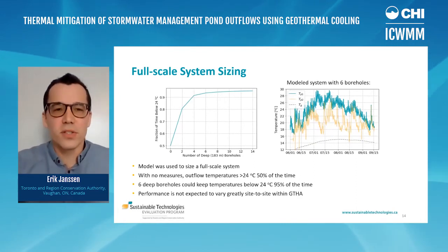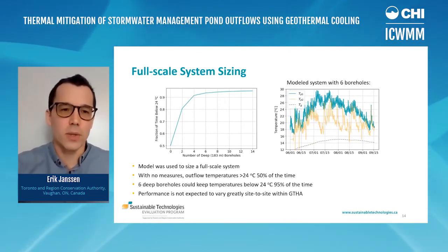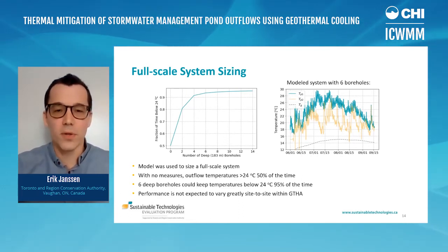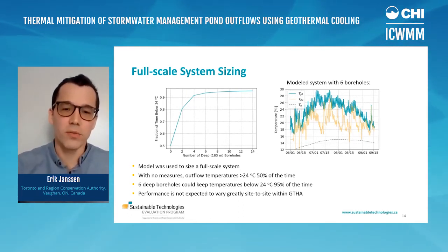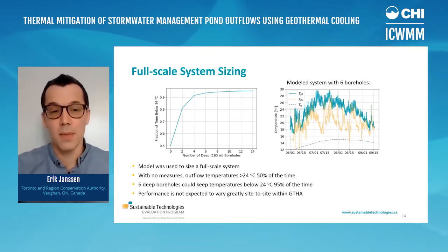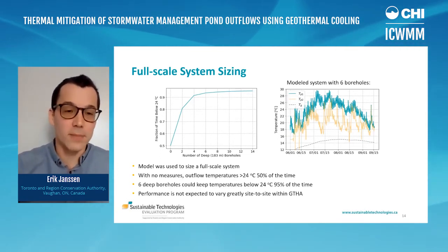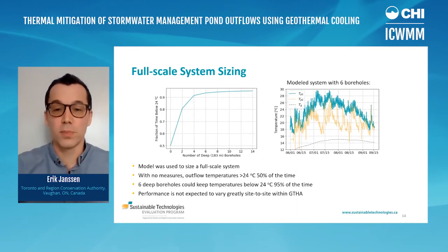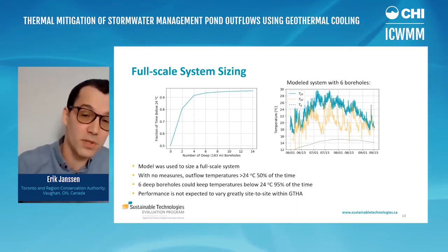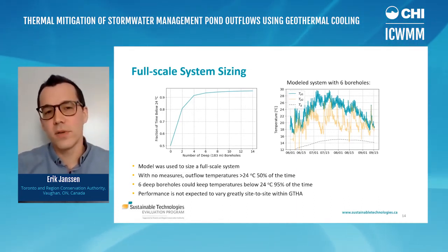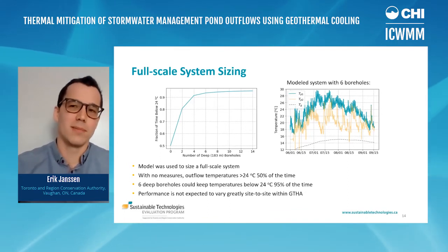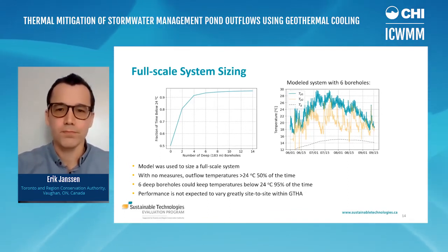We used our model to size a full-scale system that's being shown here. At the top left, you can see that with no measures in place, the outflow temperatures from the pond are greater than 24 Celsius for 50% of the time. We can use 4 to 6 deep vertical boreholes, and that could keep temperatures below 24 Celsius for 95% of the time. Beyond that, it's quite difficult because there are thermal load peaks that would need another technique to manage.